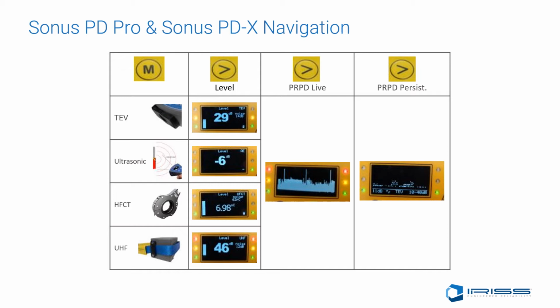This is the PRPD persist screen, which will display all the partial discharge events in a spectrogram that will appear to have rounded tops indicating the partial discharge events are occurring, and what their total amplitude is over the entire duration of the data that was collected. These clearly defined humps are the telltale signs of the presence of transient earth voltage or a partial discharge event.